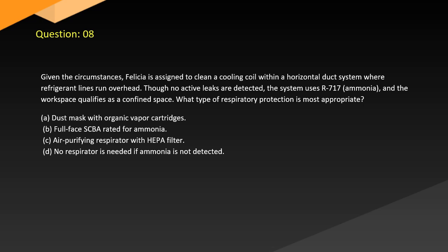Question 8. Given the circumstances, Felicia is assigned to clean a cooling coil within a horizontal duct system where refrigerant lines run overhead. Though no active leaks are detected, the system uses R717 ammonia and the workspace qualifies as a confined space. What type of respiratory protection is most appropriate? A. Dust mask with organic vapor cartridges. B. Full-face SCBA rated for ammonia. C. Air purifying respirator with HEPA filter. D. No respirator is needed if ammonia is not detected.